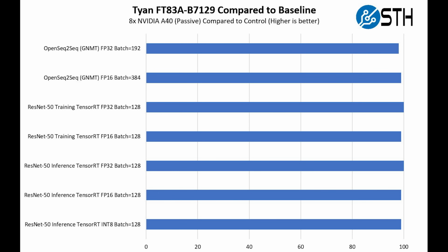We're about 1.2% on average lower than we would have expected, which is a little bit more than I would say is normal. Usually we use 1%-ish or 1.5% for our test variation. So this would probably be at the higher end of what we would consider a test variation.